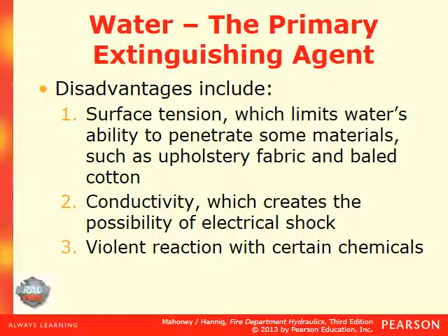So the surface tension limits the water's ability to penetrate some materials such as upholstery, fabric, and bales of cotton. The conductivity, which creates the possibility of electrical shock, is also a disadvantage. And violent reactions may occur with certain chemicals, such as magnesium.